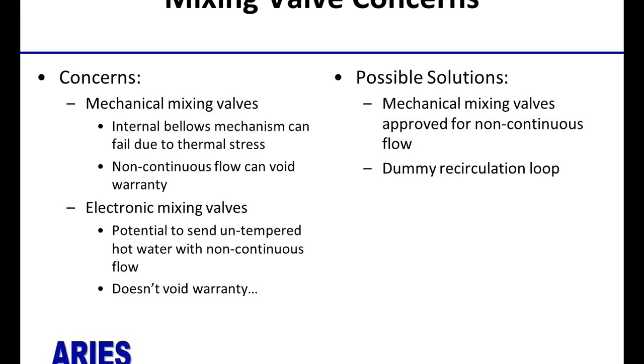Another common concern that we frequently hear is that non-continuous flow that you'd have with the demand control does not work with mechanical mixing valves. And a popular local brand will actually even void the warranty if you install demand recirculation controls. The idea being that the non-continuous flow will stress the valve to the point of failure. And with electronic mixing valves, the strictures aren't as severe, but there's still this risk that after a period of stagnant flow, when the flow resumes, there's a potential for hot boiler water to be sent through the valve to the tap at dangerous scalding temperatures.